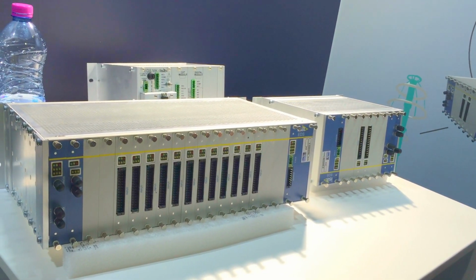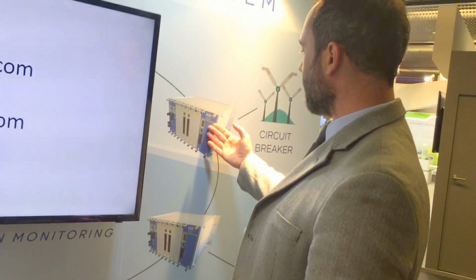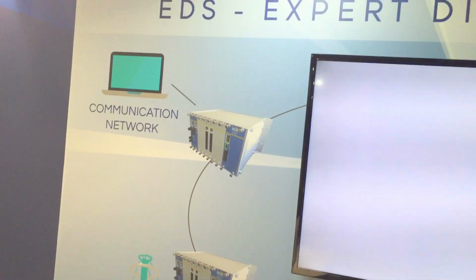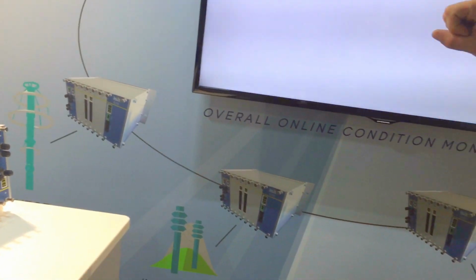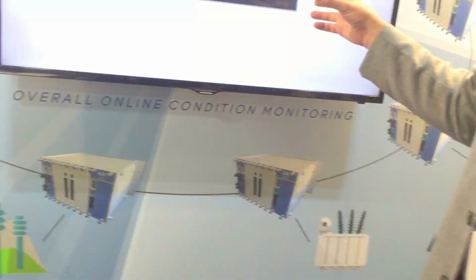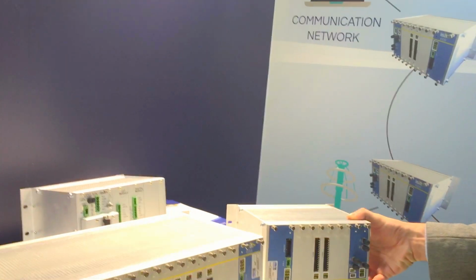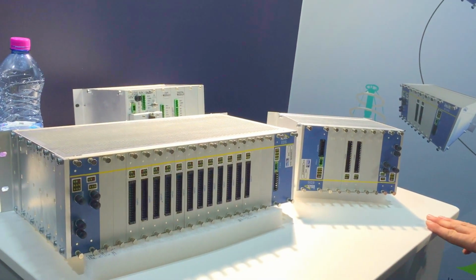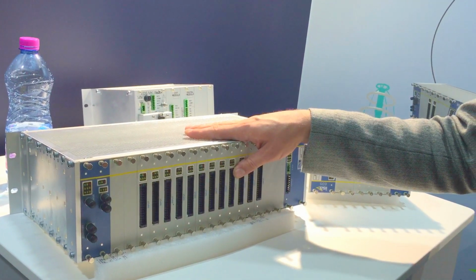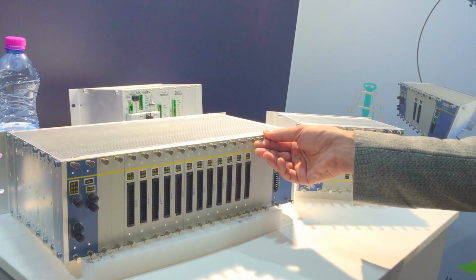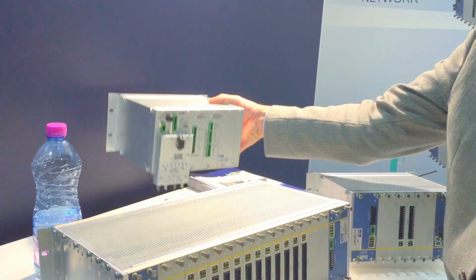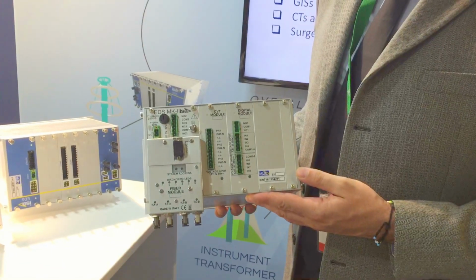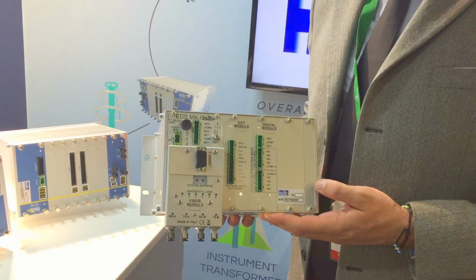EDS is a monitoring system which can monitor many things in a substation. So you can, as you can see here, monitor either a power transformer, or you can monitor a circuit breaker. It could be also in a GIS. We can monitor instrument transformers, surge arresters, and then all together connected, we go to a communication network, and using a web application, the person can see is everything okay with your primary equipment. So this would be used more for circuit breakers and for a distribution network. And this device here is a monitoring box for CVTs, capacitive voltage transformers, which is also one of the assets which we can monitor using the EDS.